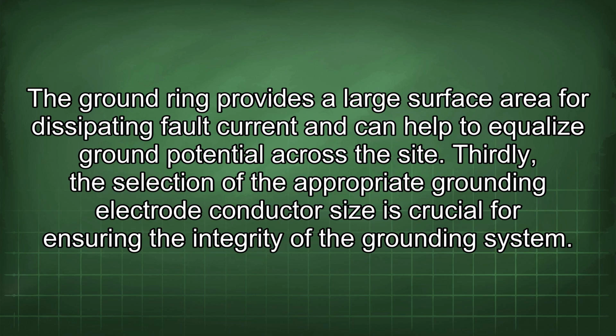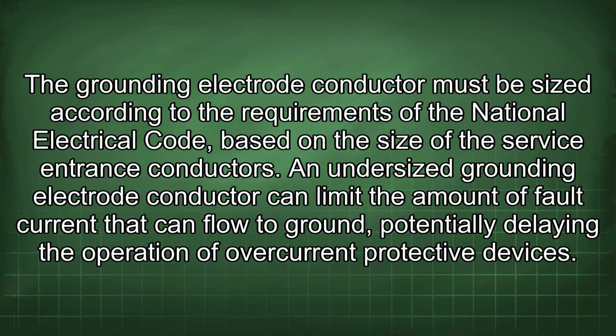Thirdly, the selection of the appropriate grounding electrode conductor size is crucial for ensuring the integrity of the grounding system. The grounding electrode conductor must be sized according to the requirements of the National Electrical Code, based on the size of the service entrance conductors. An undersized grounding electrode conductor can limit the amount of fault current that can flow to ground, potentially delaying the operation of overcurrent protective devices.